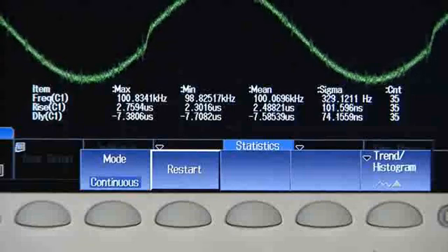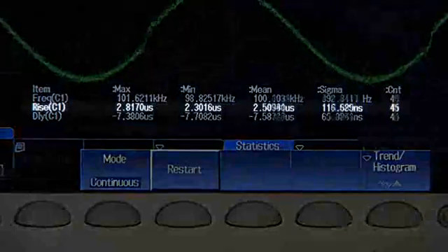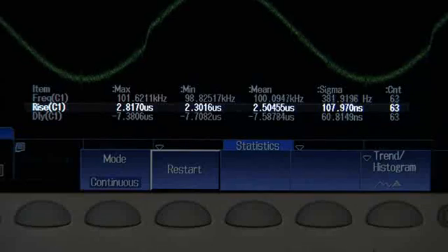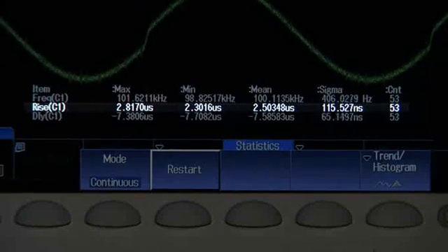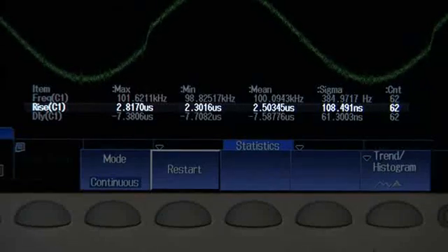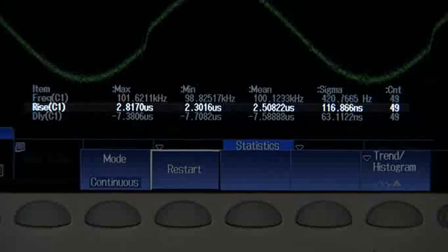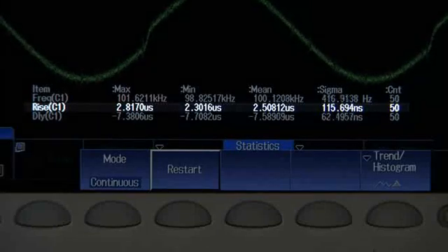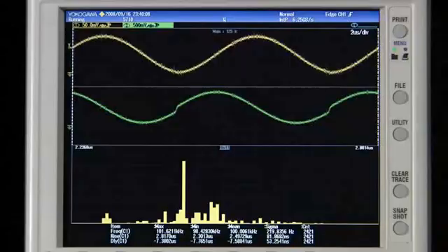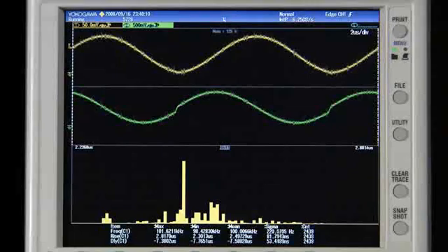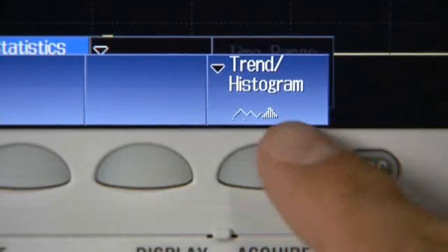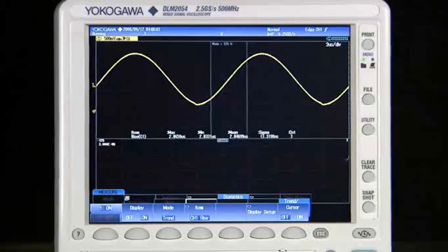For example, here we are calculating rise time statistics over multiple acquisitions, including max, min, mean, and standard deviation. The DLM2000's analysis engine can also create trends and histograms.